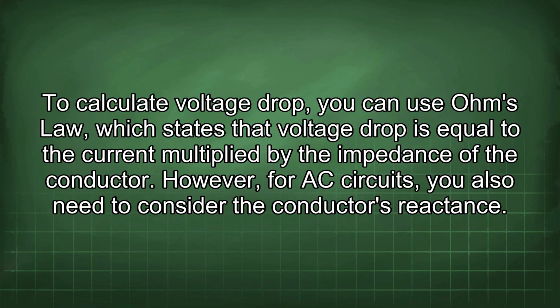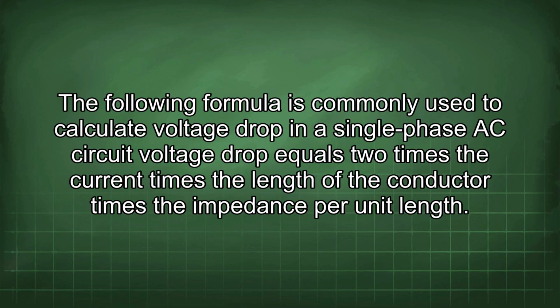To calculate voltage drop, you can use Ohm's law, which states that voltage drop is equal to the current multiplied by the impedance of the conductor. However, for AC circuits, you also need to consider the conductor's reactance. The following formula is commonly used to calculate voltage drop in a single-phase AC circuit. Voltage drop equals 2 times the current times the length of the conductor times the impedance per unit length.